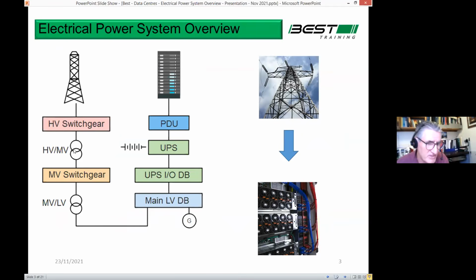And we transform down through the transformer here from high voltage down to medium voltage. Now, this whole aspect of it, the connection to the transmission system, the high voltage switchgear and the high voltage transformer, is usually done as a specialist contract outside of the normal building services contract. So the normal building service engineer that has designed the electrical system in the data center doesn't very often get involved in this. And I won't be either, because it's not my area of expertise.